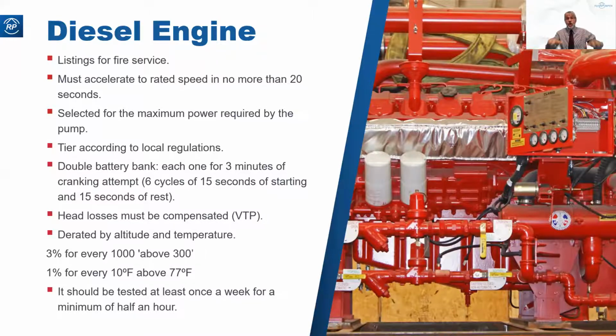And the battery banks alternate. So you have a 15-second start attempt from one, a rest period, then a 15-second start attempt from the other, and then back to the first set, and so on, until you've gone through 6 cycles, 3 from each. Then it would sound an alarm to say the engine's failed to start.